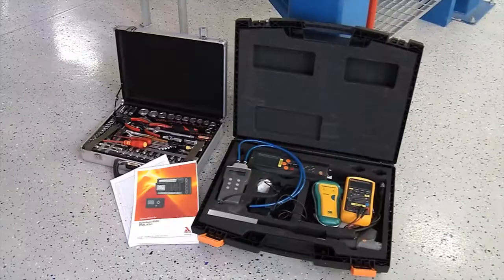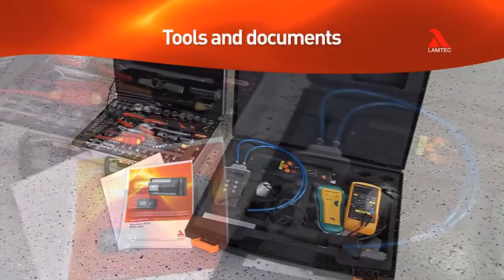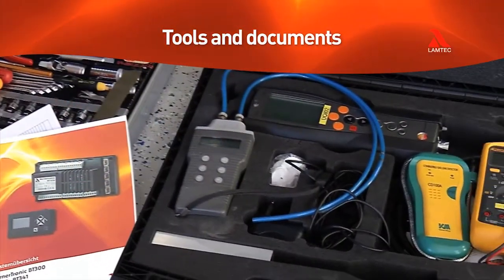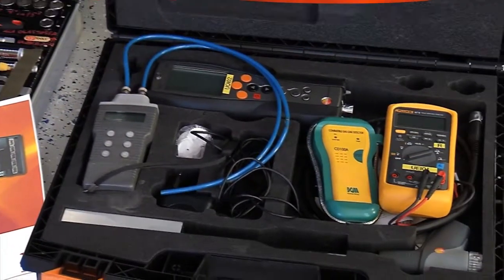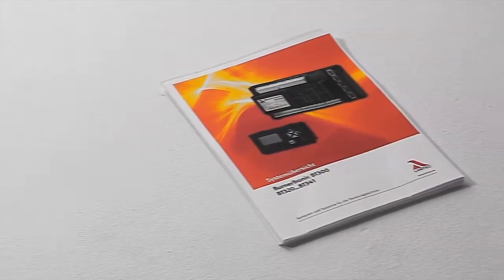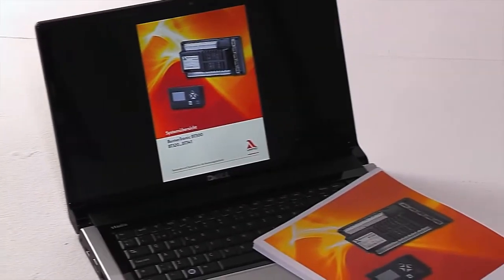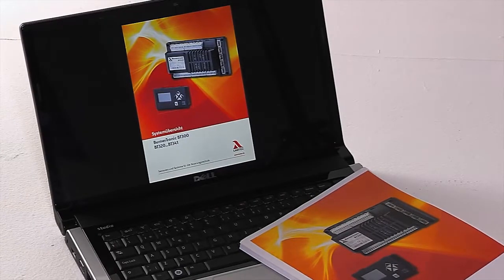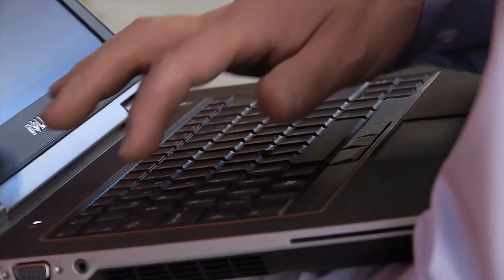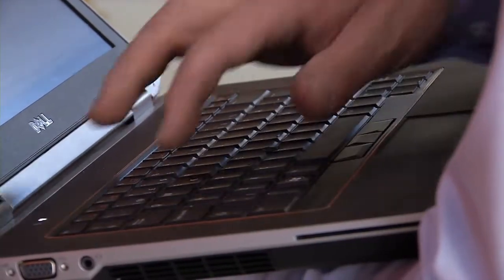Before you start commissioning or servicing the burner, check that you have all the necessary tools and documents. You will need the BurnerTronic BT300 manual, either a paper copy or a soft copy on a laptop. Make sure you know the system password in case you need to log into the system. You may also use a laptop for storing and restoring system data.